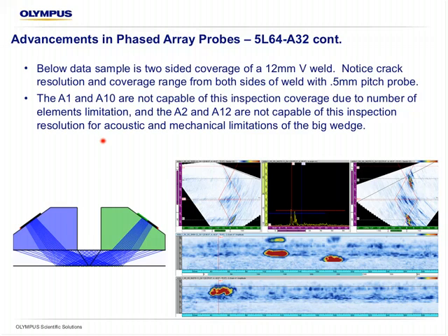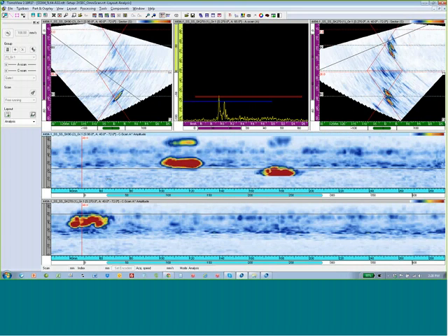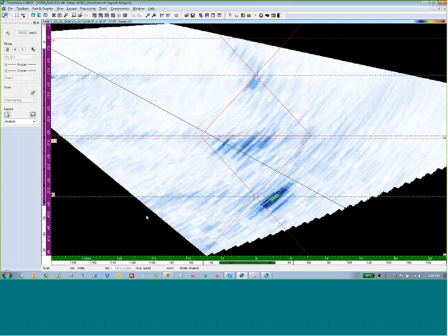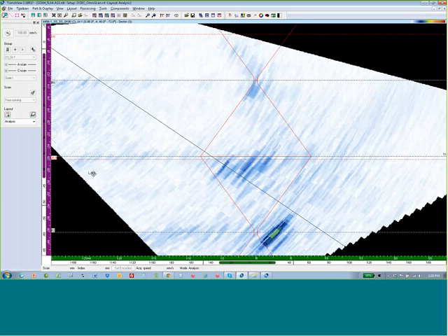An example of a data file acquired with the 5L64A32 would be a duplex weld such as we see here. This is a 12.5 millimeter V weld using a compound S-scan from 40 to 72 degrees, and we can see the coverage on the ID is more than enough to satisfy a typical B31 heat-affected zone or EN type HAZ requirements. And on the full skip to the cap, we see enormous amount of coverage.